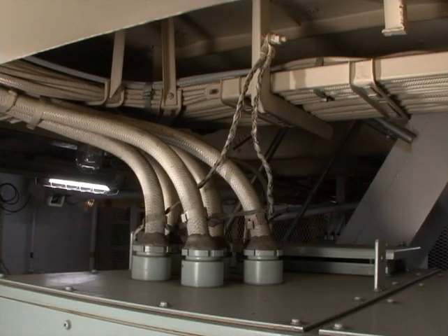It is difficult to resolve the fundamental causes of harmonic current problems on board. However, one effective measure is to keep the transmission and signal lines away from each other. It is also advisable to confirm that the line has been properly grounded. For example, when the transmission line is covered with basket armor, grounding of the basket armor should be confirmed.